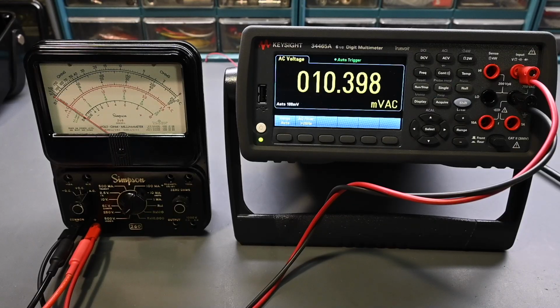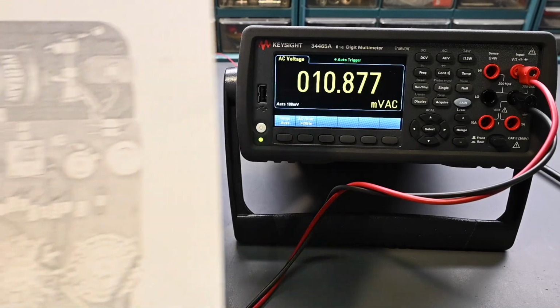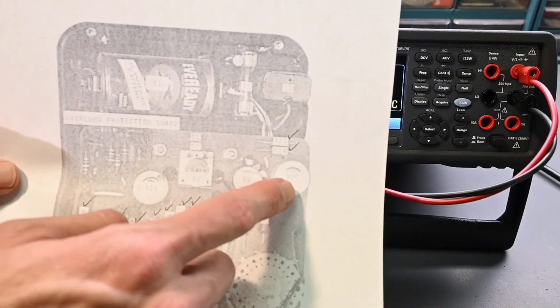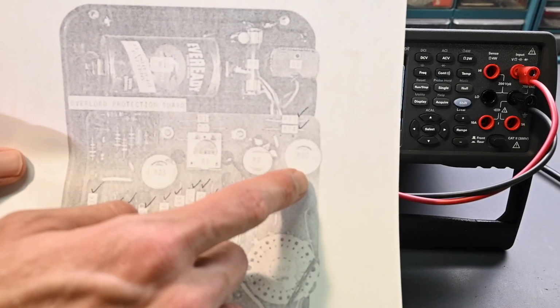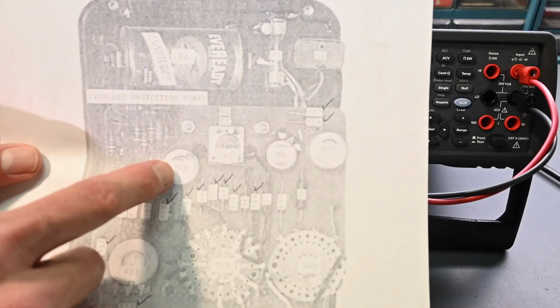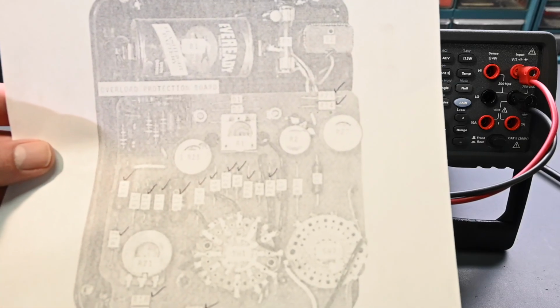Now there is some minor interaction between the 2 calibrations, so after you do the calibration once, you probably should go back and check it a second or maybe even a third time. Just continue until no further adjustment is necessary. I'll go through the calibration once on camera, and then any further touch-ups I'll just do off camera. All right, so taking a look at this drawing right here, you can see this potentiometer is R22, and that's used for the 250 volt adjustment, and R25 is used for the 2.5 volt adjustment.